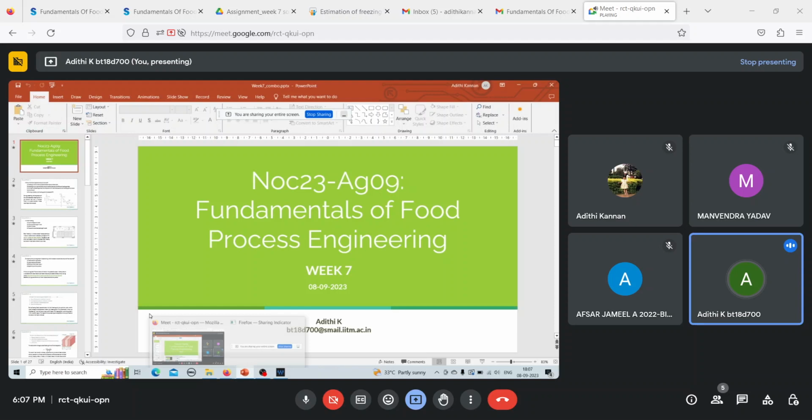Plank's equation is a much simpler process compared to the longer Cleland's equation. So we calculate delta T2, which is Tfm minus Ta. Tfm is minus 7.134, which we calculated, and Ta is minus 40 degrees, which comes out to be 32.87 degrees Celsius. So now we have delta T1 and delta T2. We need to calculate delta H1 and delta H2.